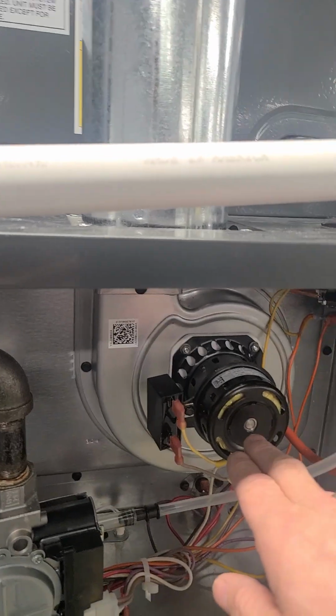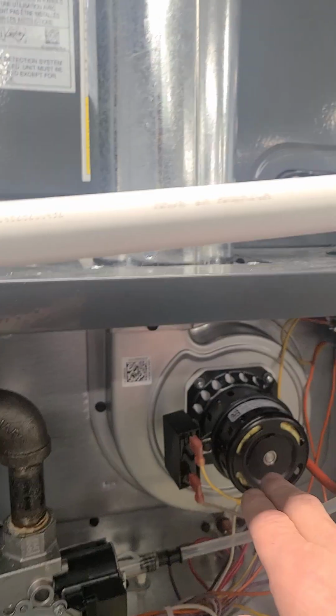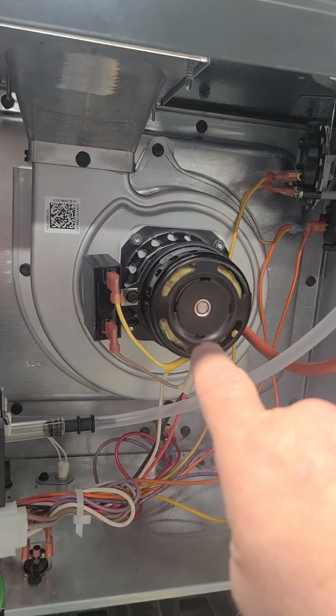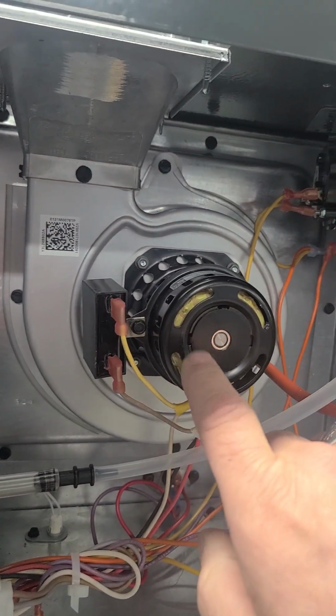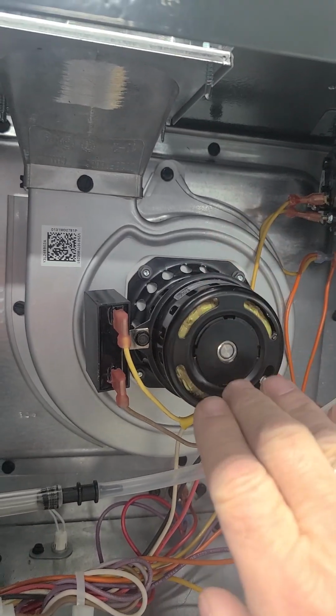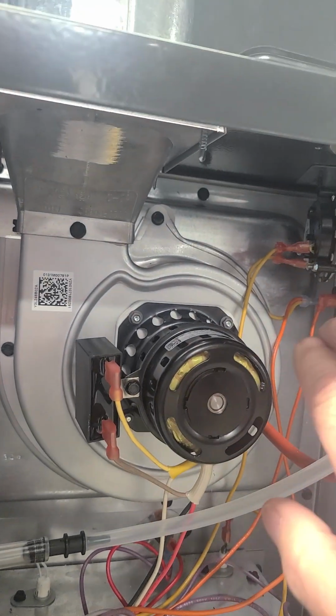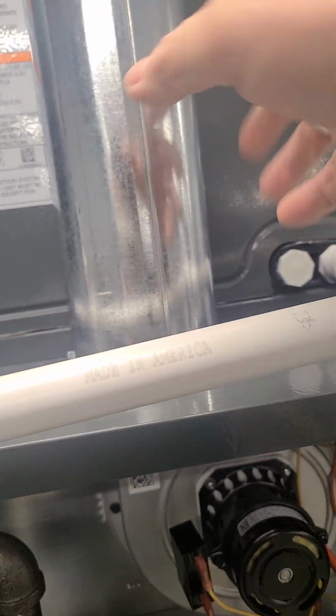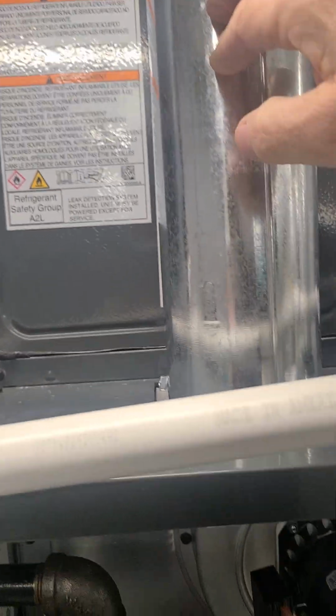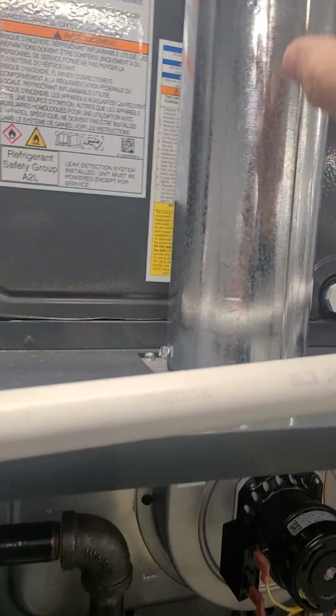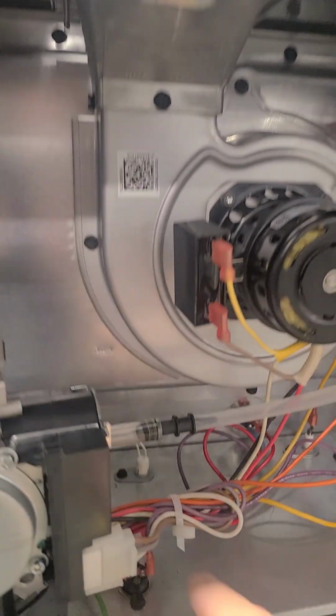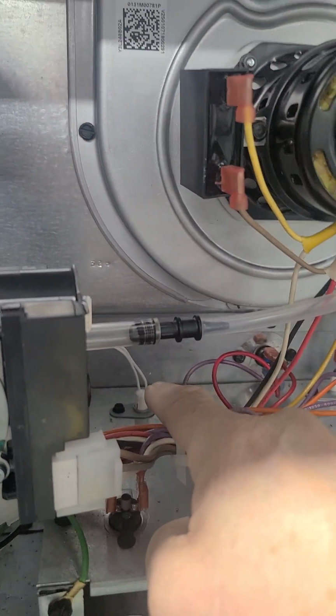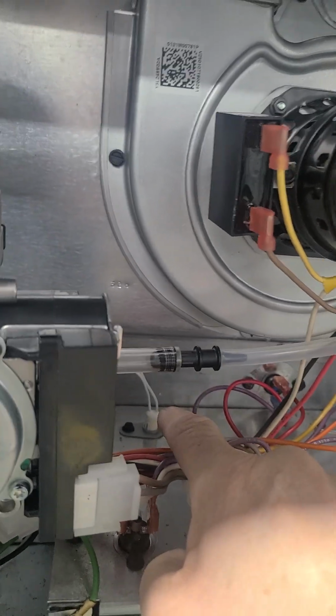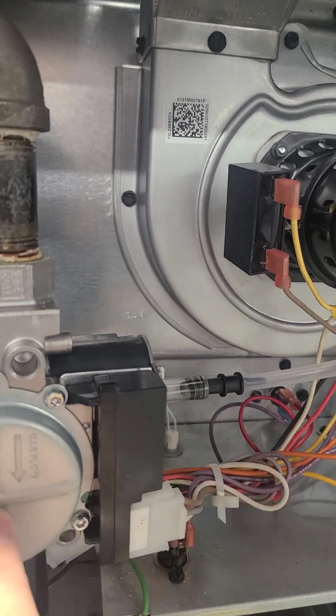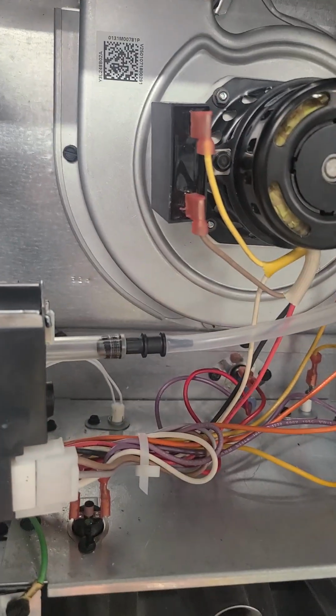It will start a 15-second pre-purge in high speed with the inducer blower motor, and then shut down, or not shut down, but reduced to a lower speed. And then the pressure switch should, if everything is okay and the flue is open and working correctly, sense a negative pressure in the flue. And then once that negative pressure is sensed, the igniter will go on a warm-up period, and after the warm-up period, the gas valve will open, sending gas down to the burners.